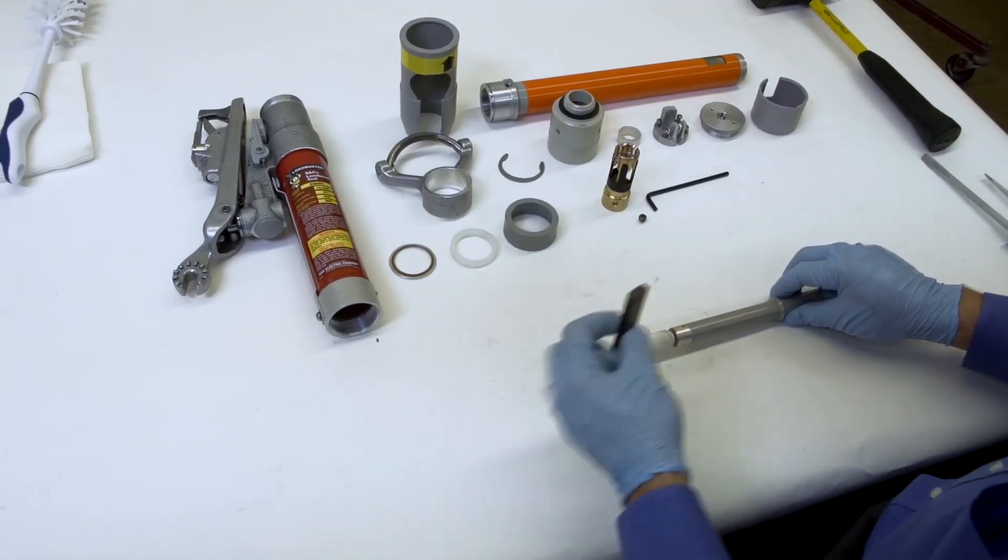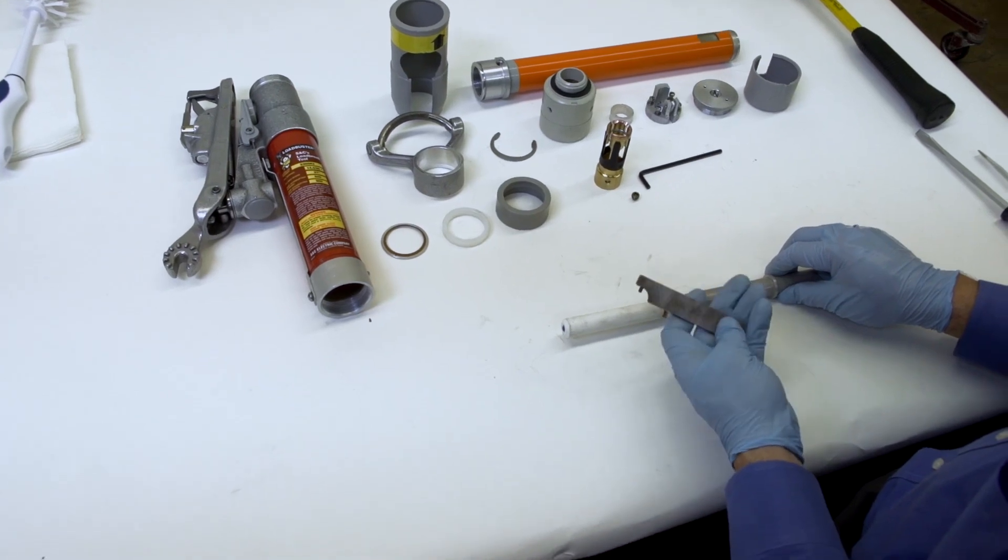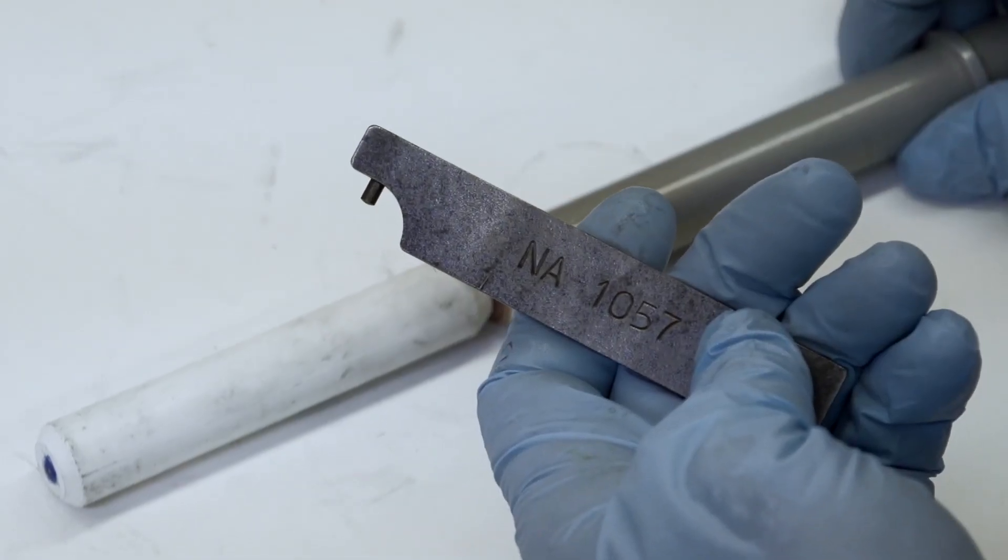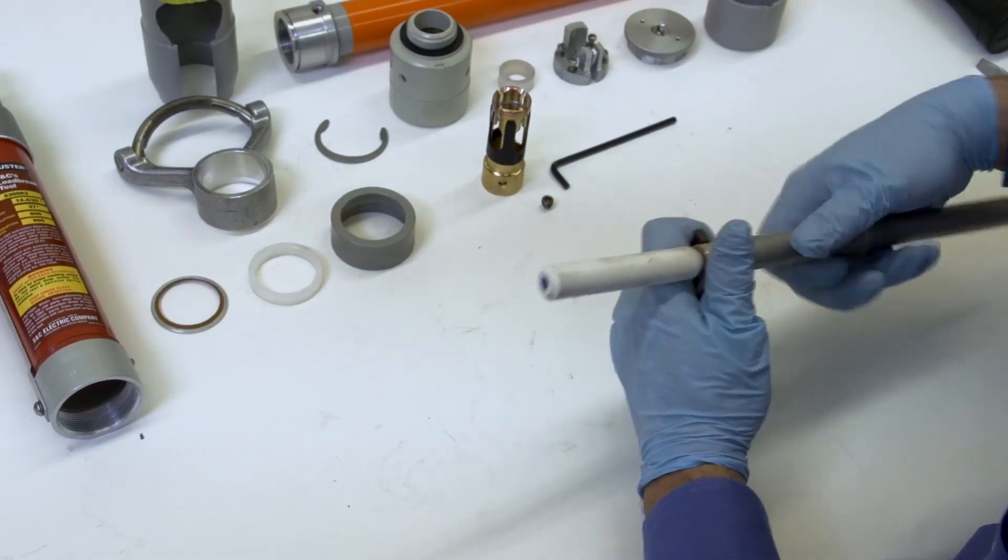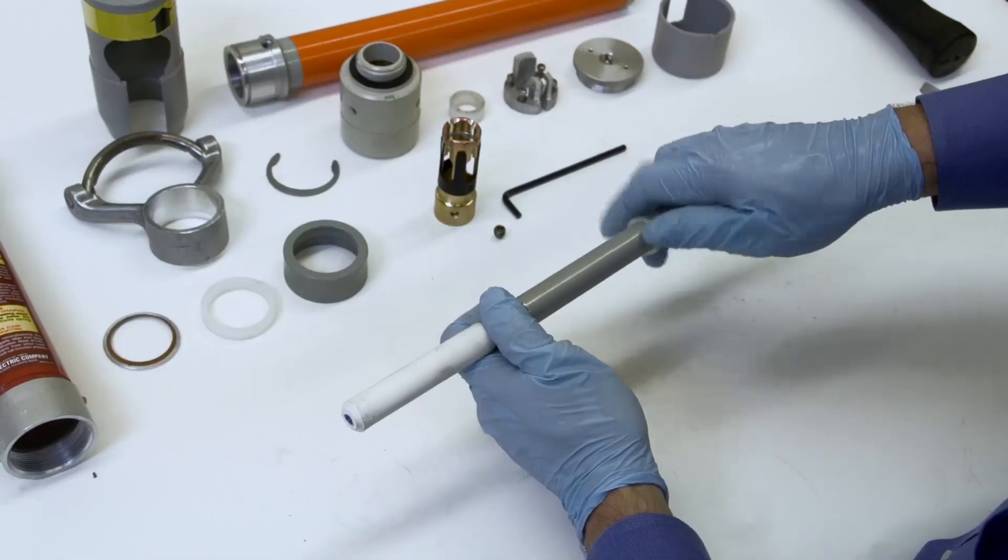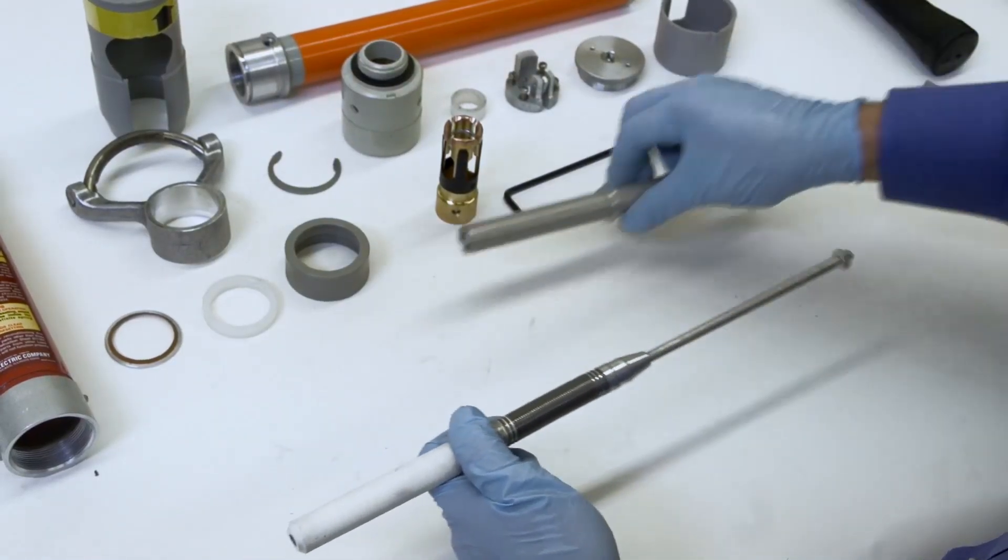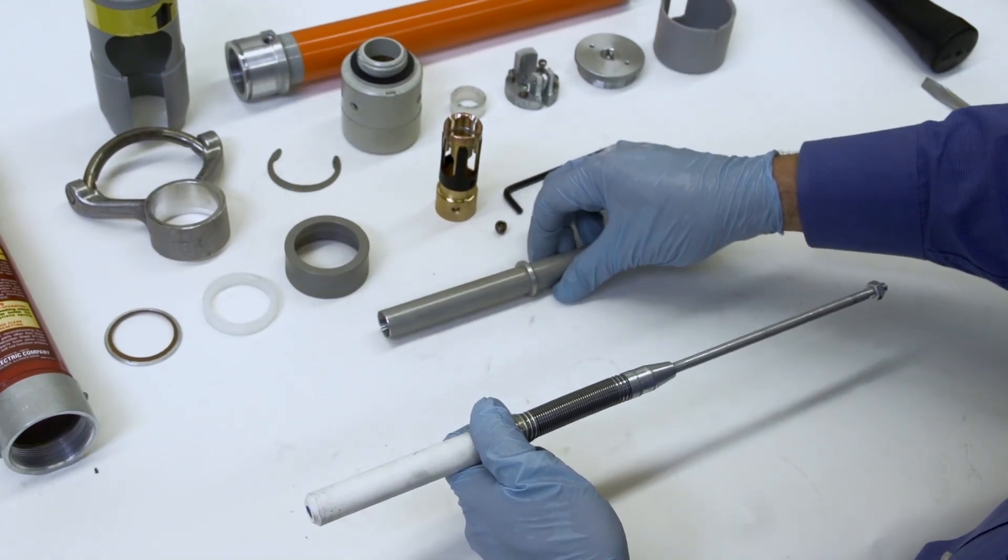Unscrew the contact tube from the moving contact assembly using a drift pin or S&C spanner wrench NA1057. Remove the tube. This completes disassembly of the Loadbuster tool.